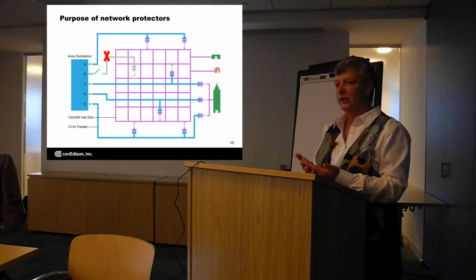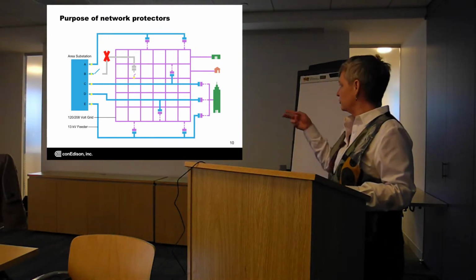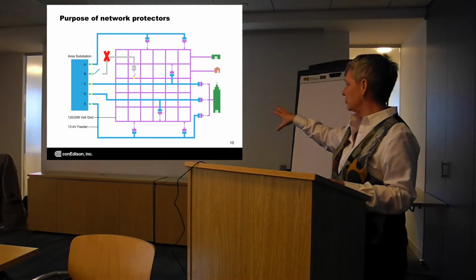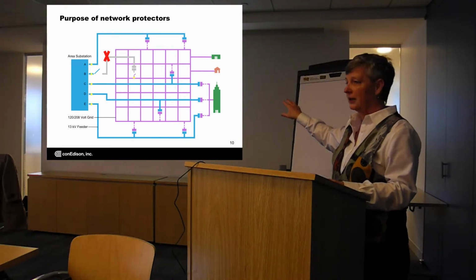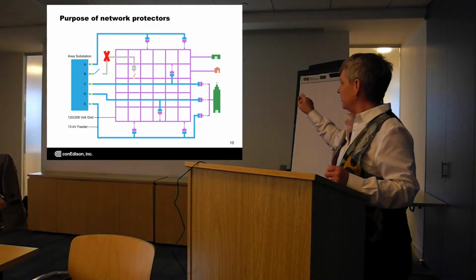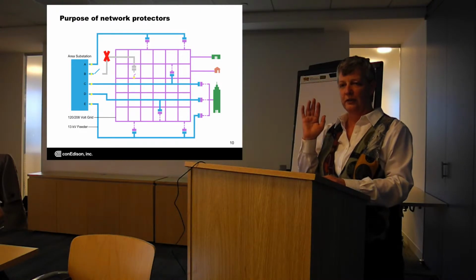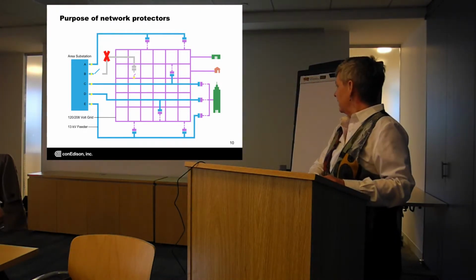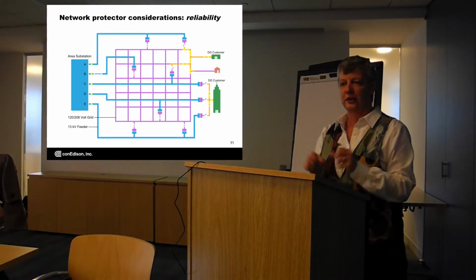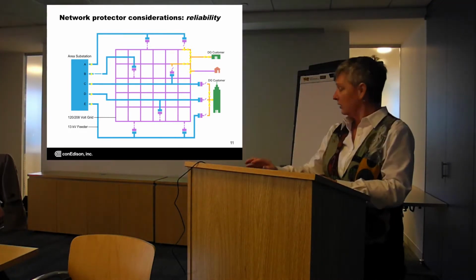And so when we do upgrades to the system for expected increases in load, it's to make sure that we meet this design basis, what we call N-2, two major components out of service and still supplying the load for this network. But a key piece of this design is that those network protectors will open if there's any flow going backwards. And so if you install generation at the customer side, you can be pushing energy back out into the network, and you can open those network protectors.